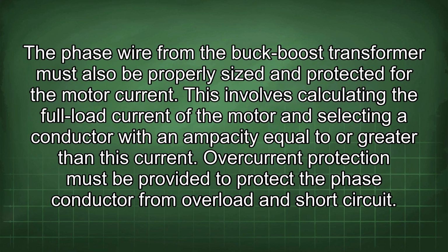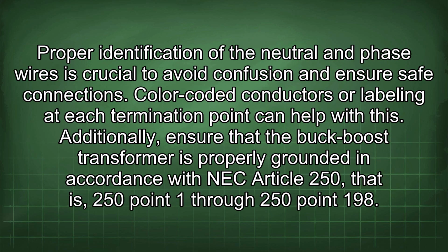Phase wire from the buck-boost transformer must also be properly sized and protected for the motor current. This involves calculating the full load current of the motor and selecting a conductor with an ampacity equal to or greater than this current. Overcurrent protection must be provided to protect the phase conductor from overload and short circuit. Proper identification of the neutral and phase wires is crucial to avoid confusion and ensure safe connections. Color-coded conductors or labeling at each termination point can help with this.